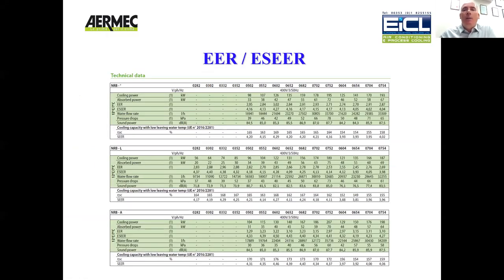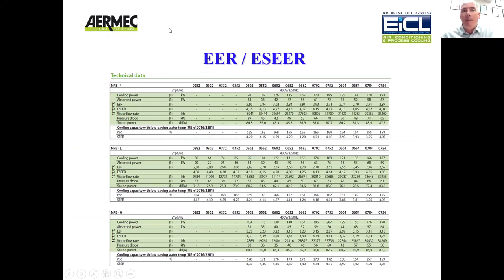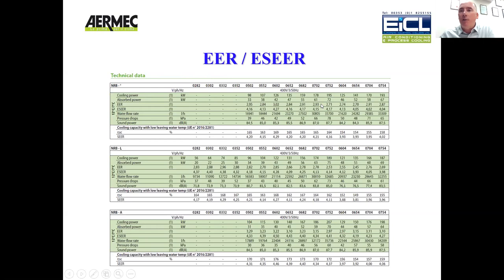If you look at any chiller manufacturer's catalogue, you will typically have a number of options: a standard, a low noise, high efficiency, an elevated unit, super low noise, super high efficiency, and so on. This is an extract from an AERMEC product guide — we represent AERMEC in EICL. If you look at the various models and capacities, you will have cooling capacity and then you will have an absorbed power. Basically, your cooling capacity divided by your absorbed power is your EER — your energy efficiency ratio at 100% load. That's very important to know.